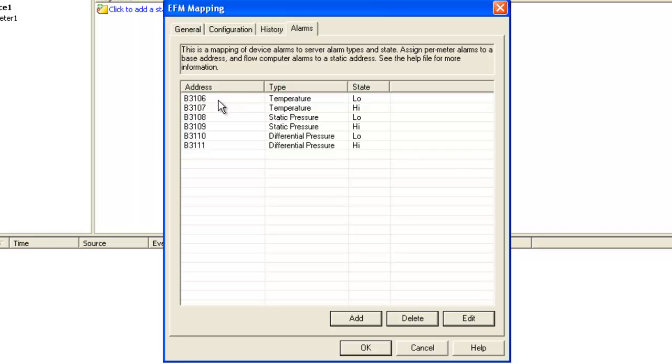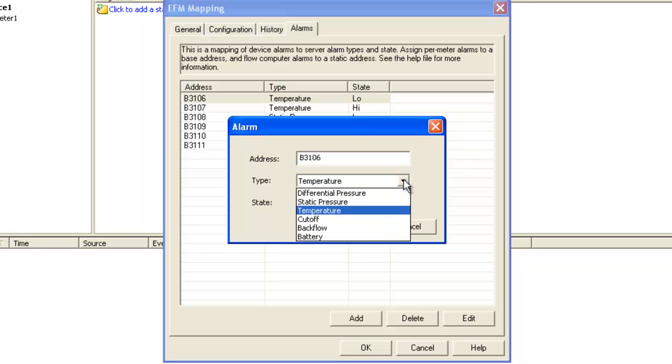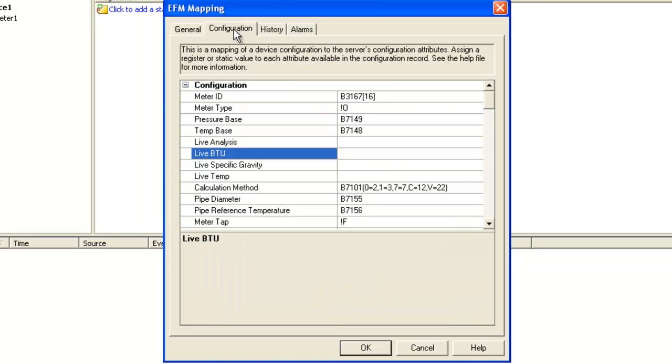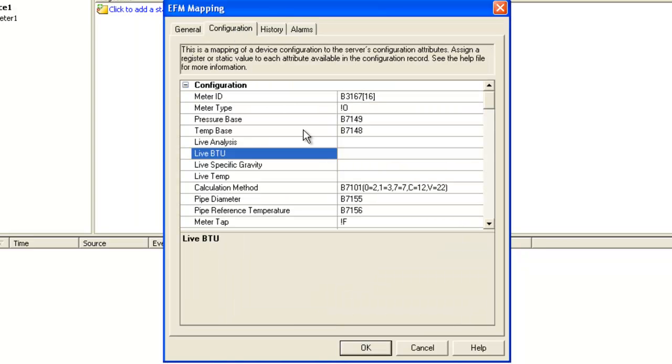Now alarms are very similar to configuration data. They use the base address syntax, so if I get an alarm from 3106, I know that that's meter 1. It's a temperature alarm that's set to the low state. Event or audit data is actually based off the configuration data. So again, if I get an event from 7155, I know that that's a pipe diameter audit event for meter 1.